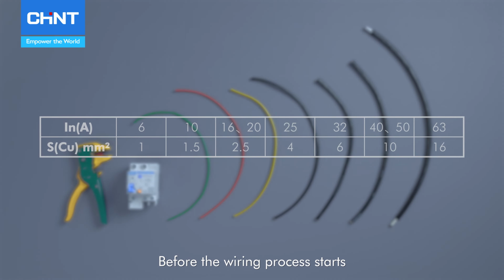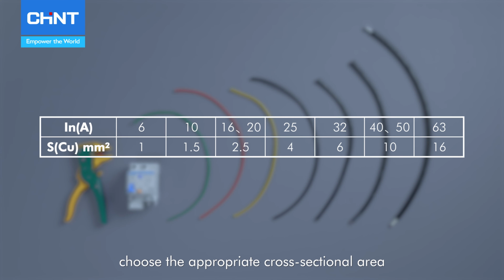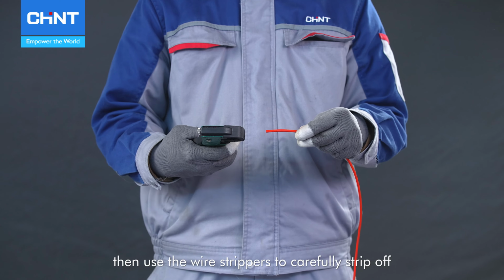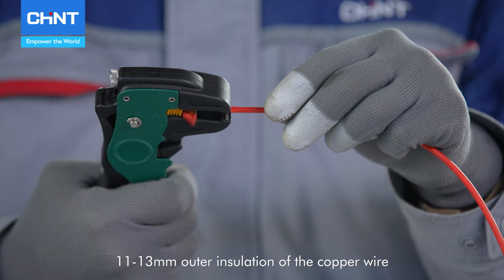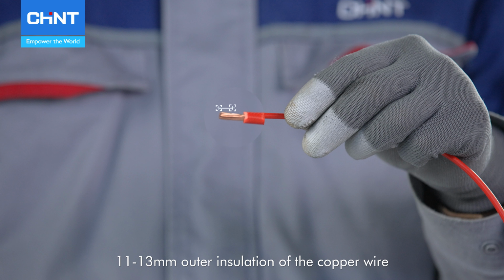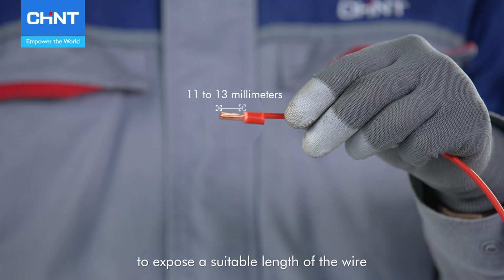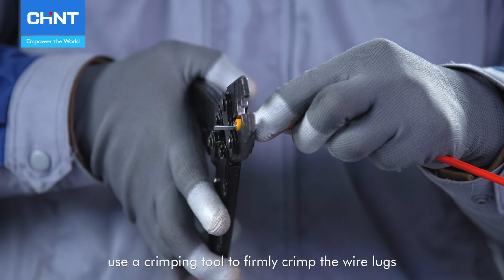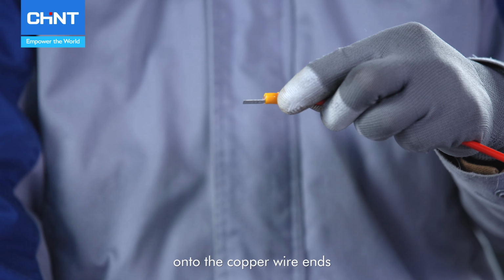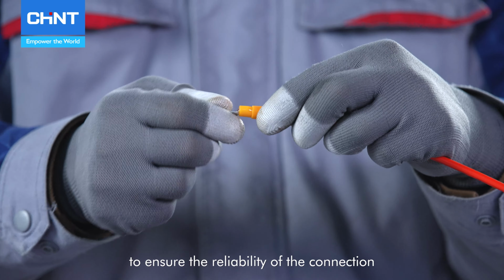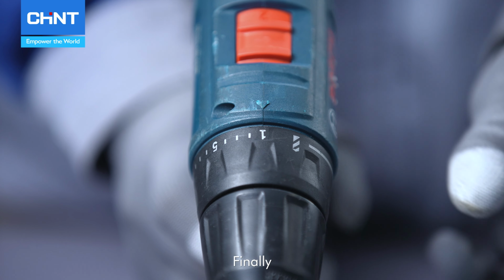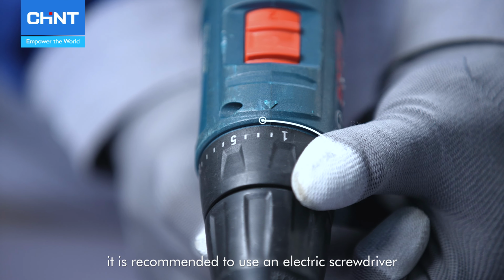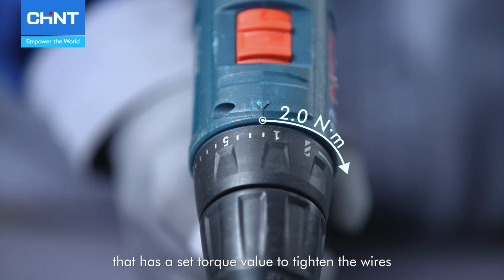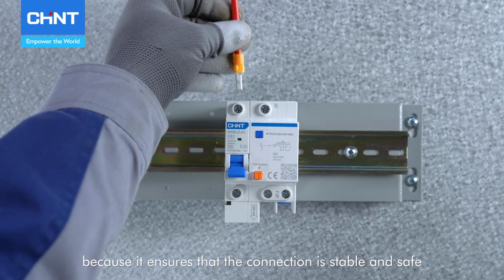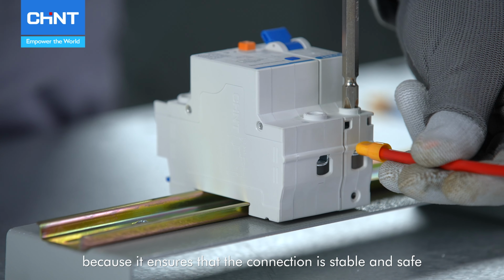Before the wiring process starts, choose wires with the appropriate cross-sectional area based on the product's current rating. Then use a wire stripper to carefully strip off 11 to 13 mm outer insulation of the copper wire to expose a suitable length of the wire. Next, use a crimping tool to firmly crimp the wire lugs onto the copper wire ends to ensure the reliability of the connection. Finally, it is recommended to use an electric screwdriver that has a set torque value to tighten the wires. This is important because it ensures that the connection is stable and safe.